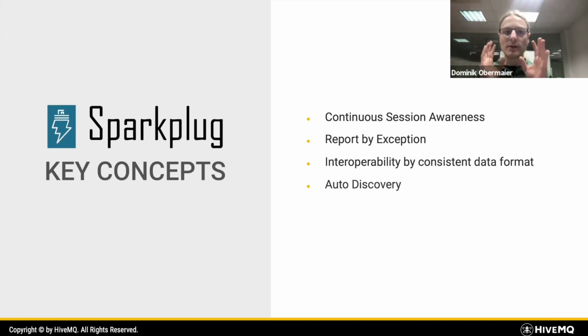MQTT, as I said, is push-based. This means, say you want an update of your PLC and you want to read some values. What you would do with polling is go to your PLC every 5 seconds and ask, hey, did something change? Then you get a new value. But it could happen that the value doesn't change at all for a very long time, so you're basically wasting bandwidth and compute power doing something that isn't required.